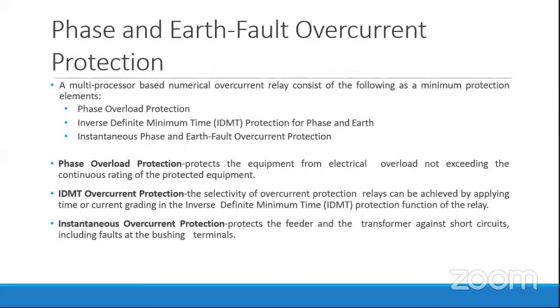Another protection is termed IDMT overcurrent protection. The selectivity of the overcurrent protection relay can be achieved by applying, as I said, time or current grading in inverse definite minimum time protection functions. Another protection is instantaneous overcurrent protection, which protects the feeder and transformer against short circuits, including bushing terminal faults of the transformers or its switchyard. The ANSI code for instantaneous overcurrent protection is 50. For IDMT, that is time overcurrent inverse definite time protection, it's 51. And thermal overload, that is phase overload protection, the ANSI code is 49.